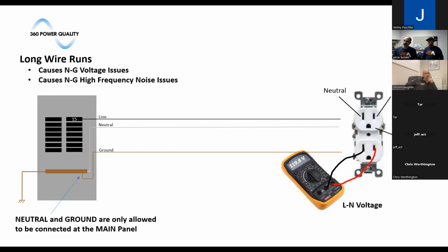So ground and neutral get terminated to the same spot. We all know that if two wires are terminated to the same spot, the voltage between them should be zero, right? So that's kind of the assumption that equipment manufacturers make: that neutral and ground are zero.